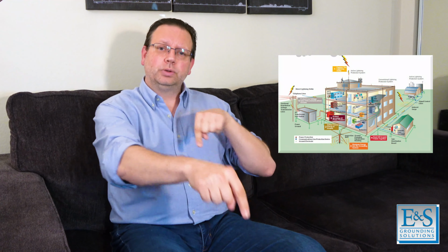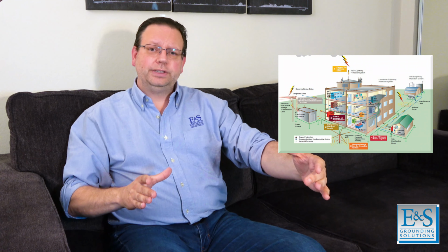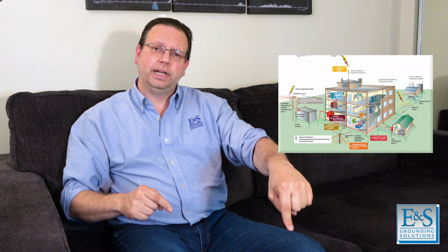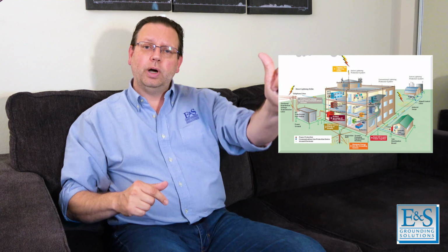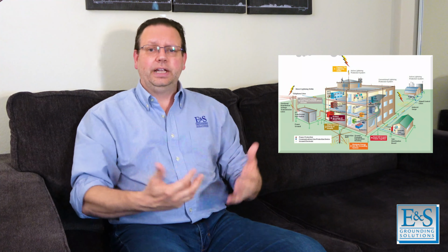If we don't have a ground loop and we only have individual ground rods, then that becomes a fault current path. So say the wave hits your northeast corner and you just have a simple ground rod on your lightning protection down conductor, it'll go up over your system and down, causing magnetic fields to form inside of your structure. And again, you could suffer damage because you failed to have a ground loop.